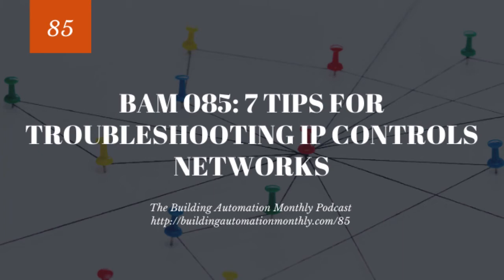All right, so here is what I mean by that BBMD. You've got those BBMDs, and you've set them up in the network segments. Well, sometimes something happens, and you lose one of the BBMD IP addresses, and then all of a sudden your BACnet messages are no longer being routed. So it's really important for you to understand that as well. It's also important to understand that those BBMD tables need to be on devices that have static IP addresses. You don't want your BBMD being assigned a DHCP address. That would really mess with things. That gets really ugly really fast.